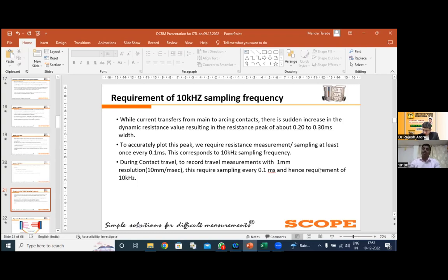So there is a sudden or drastic change in the resistance value, and it reaches the peak within a span of 0.2 to 0.3 milliseconds, which is very small. That's why the 10 kc or 10 kilohertz sampling speed is required. Why? One more thing is how it fulfils the requirement.